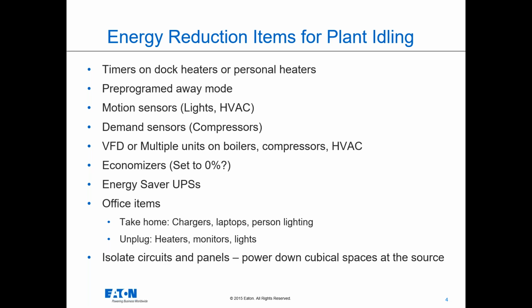You're able to shut some down and leave others running, which might be a way to save energy during a shutdown. Or this isn't just for shutdowns, right? For curtailments, if you're not running a lot of heat generating equipment, you might not need as much HVAC capacity, and you might be able to turn off the least efficient HVAC units. So if you have one or two that you know aren't as efficient as the newer ones, shut those down first, and you'll save more money that way.